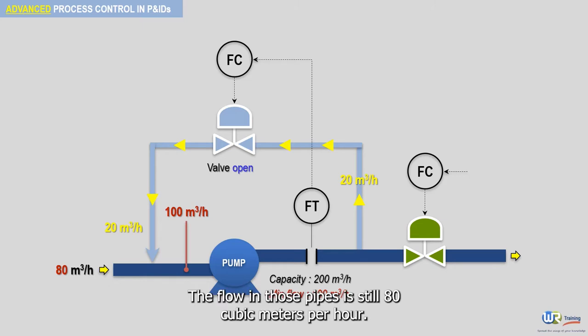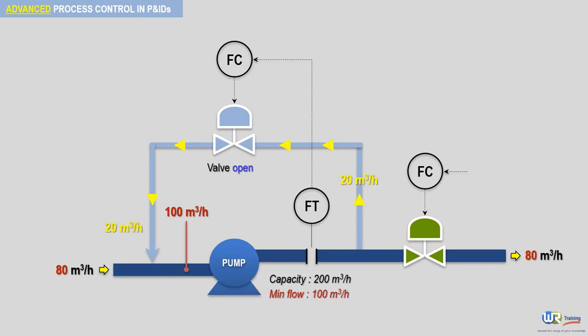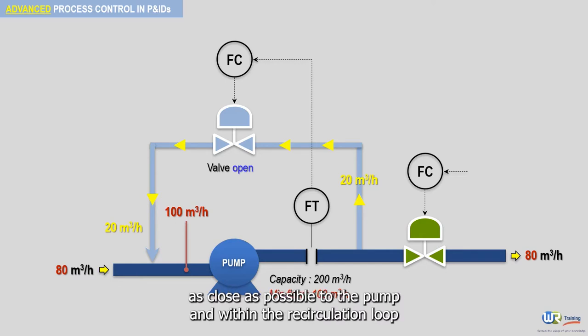The flow in those pipes is still 80 cubic meters per hour. The point here is that the sensor should be placed as close as possible to the pump and within the recirculation loop.